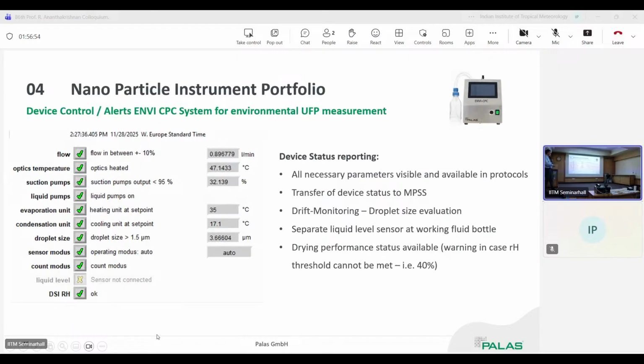The second is that we have very comfortable device status reporting. All parameters which are critical for the condensation or even for the sizing are given by the system and also reported by the respective protocols which you can use. And we have here underneath a liquid level sensor control. The liquid level sensor, something we implemented recently, shows you whether the bottle is nearly empty and then gives you 2-3 days to refill. Other devices say, okay, particle size too low, signal too low, please refill butanol, and it's already too late. We want to have it different, and that's our solution.